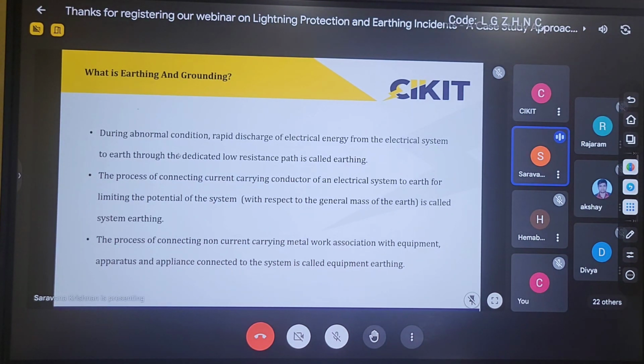Before entering into that, let's have a small introduction about earthing. The purpose of providing earthing is to divert fault current or lightning impulse current to the ground during abnormal conditions by providing a dedicated low resistance path. If I provide this connection to the equipment body, it will be considered equipment earthing or body earthing.